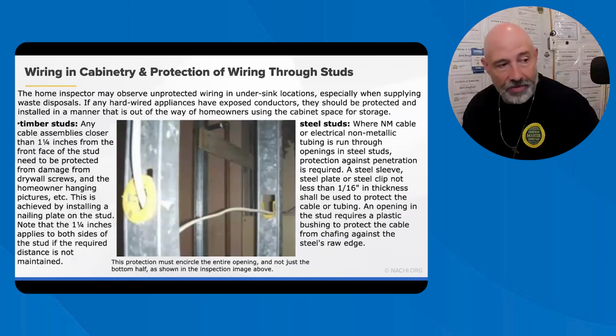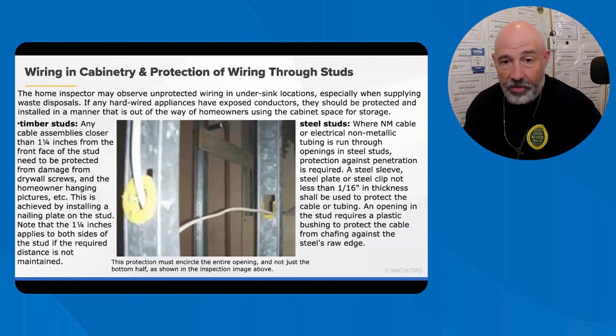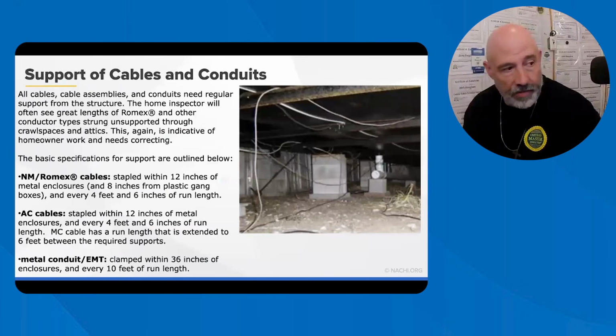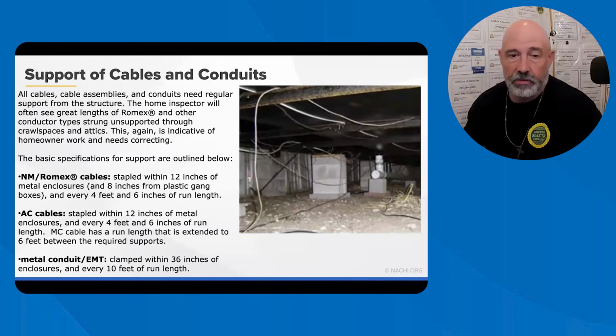Here we have a wire that's going through steel beams. Make sure that if they are going through it, they have the protective sleeve around it so that they're not cutting the wire. Matter of fact, I had a couple of wires going through a conduit that didn't have the proper bushings on there, and it's trimming up that sheathing. So here we have a lot of support cables and Romex, or the non-metallic cables.